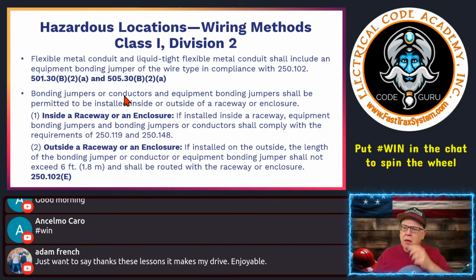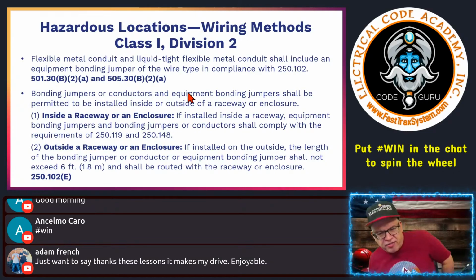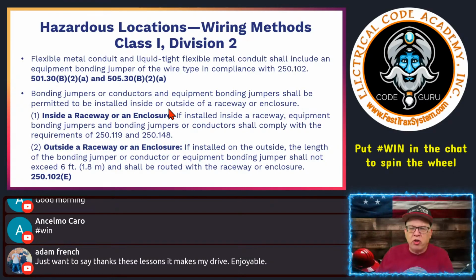All right, now, staying on that same topic of the bonding, so when you're using FMC or using LTFC, which is liquid tight flexible metal conduit, or LFMC, I guess it would be. One thing to remember is you have additional bonding where you aren't able to utilize the armor, right? And so especially in these types of locations. So it's going to make reference to 501.30(B)(2)(a) and 505.30(B)(2)(a), which again is zoning when you're dealing with 505.